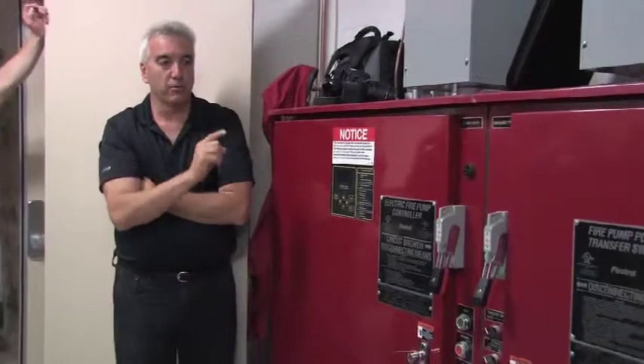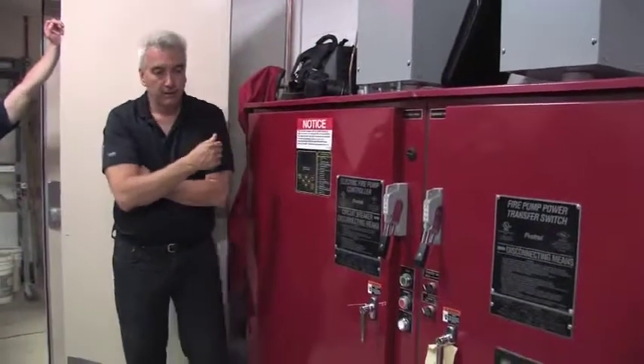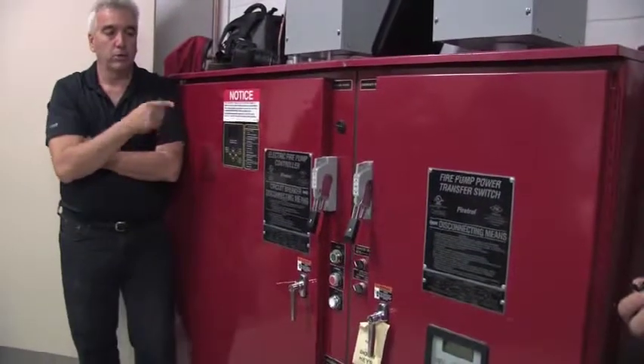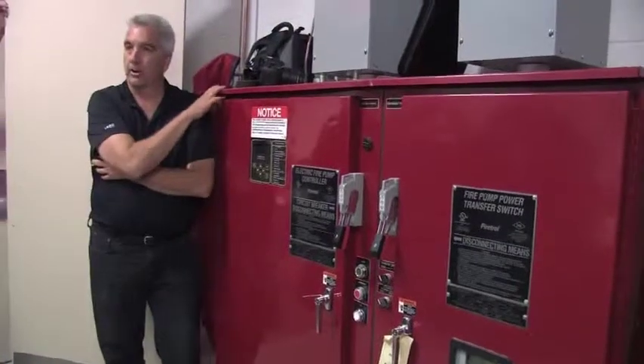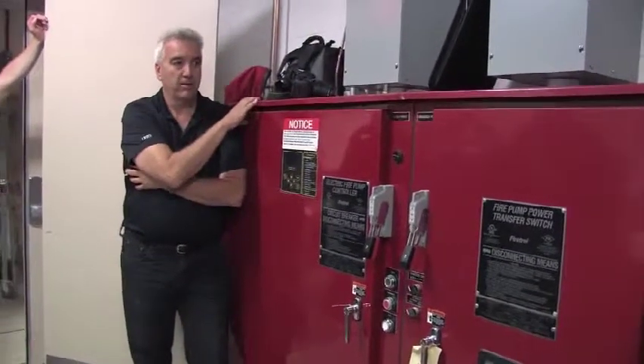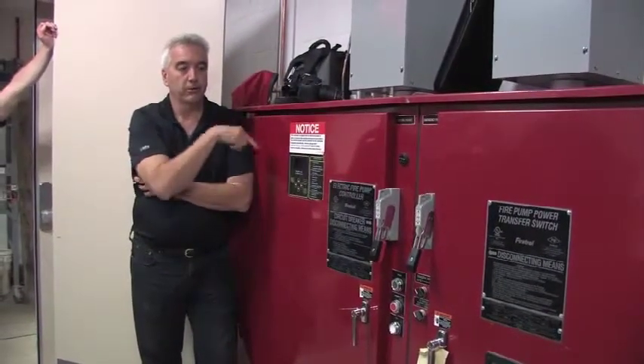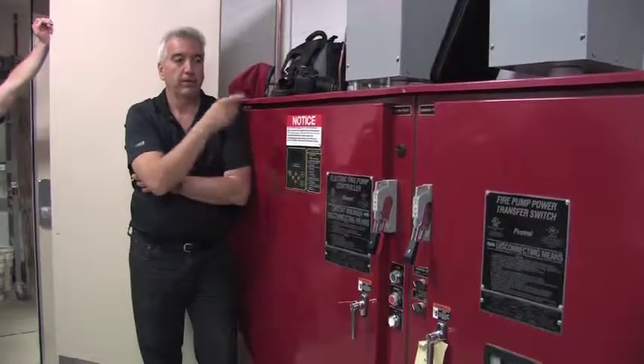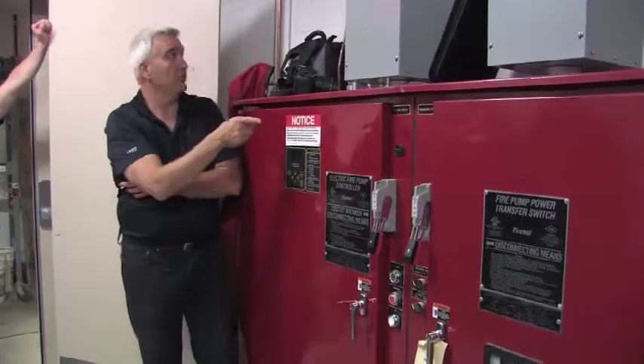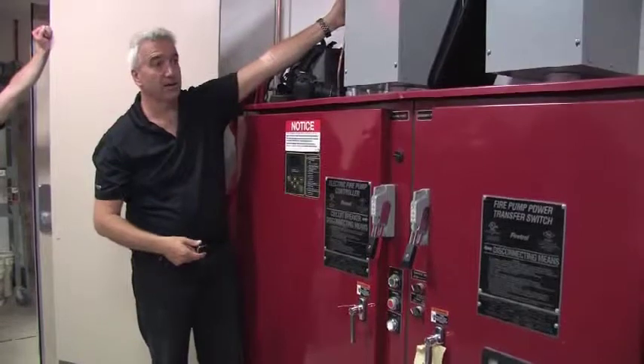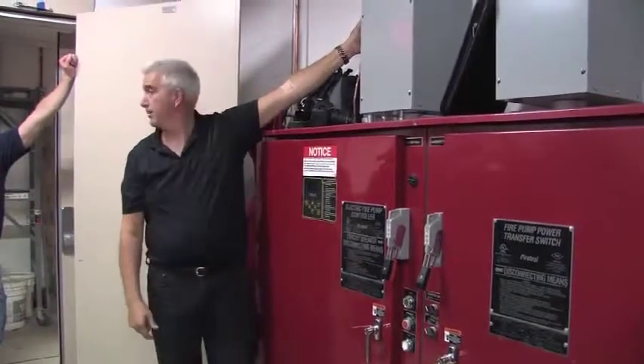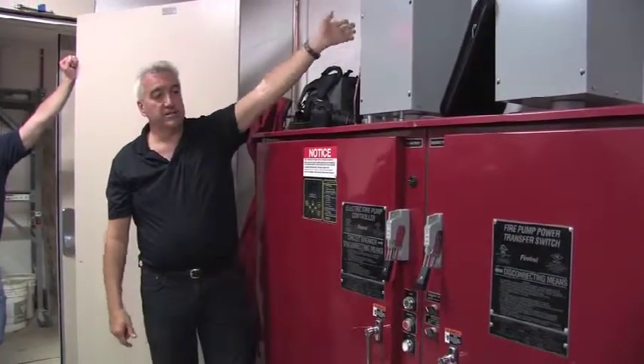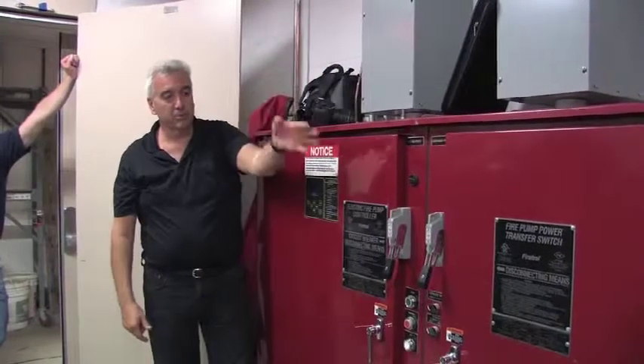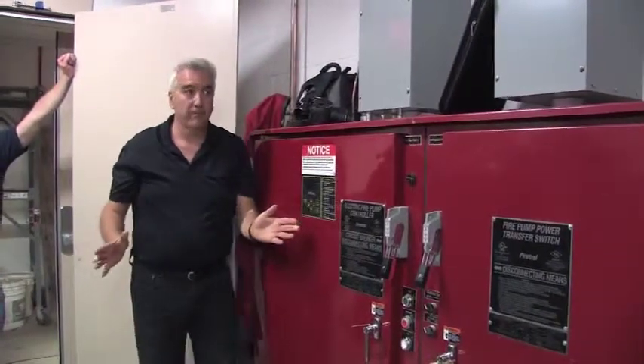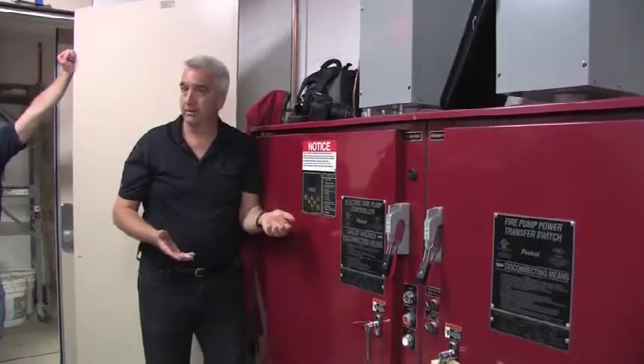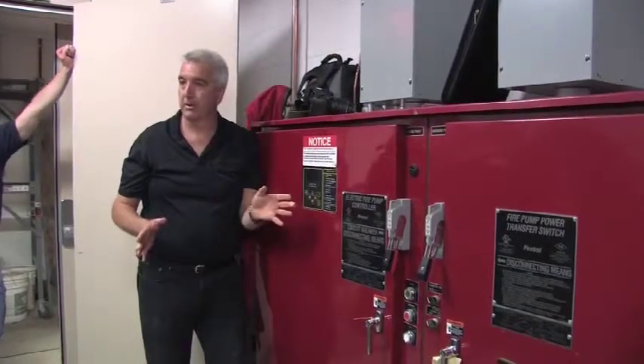Sometimes there's questions on the retransfer function. Let's say you weren't testing and you actually had a real power outage. So you lost power. This unit would start the generator. It would switch over because presumably you've got the call leads, and I bet that's what these are right here, the 2-hour fire rated cable. So this calls the generator to run, it switches over. The pump doesn't start, it's just sitting there with standby power. No need to call the pump on unless there's a pressure drop.